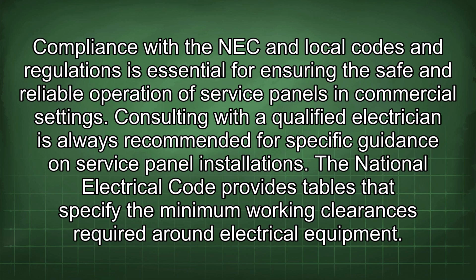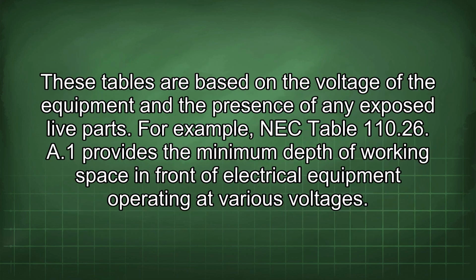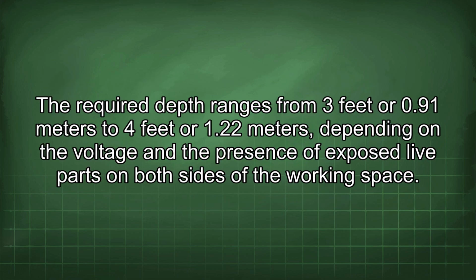The National Electrical Code provides tables that specify the minimum working clearances required around electrical equipment. These tables are based on the voltage of the equipment and the presence of any exposed live parts. For example, NEC Table 110.26(A)(1) provides the minimum depth of working space in front of electrical equipment operating at various voltages. The required depth ranges from 3 feet or 0.91 meters to 4 feet or 1.22 meters, depending on the voltage and the presence of exposed live parts on both sides of the working space.